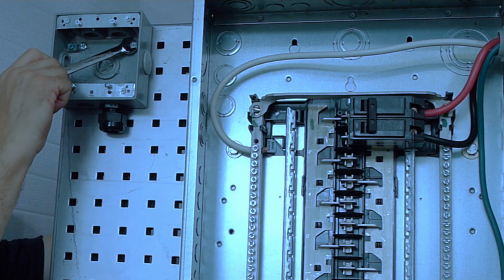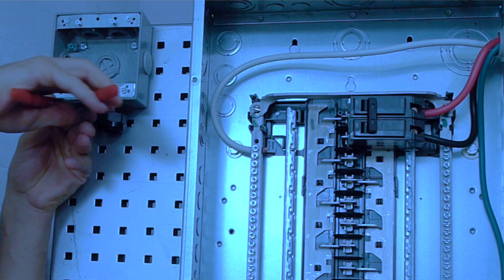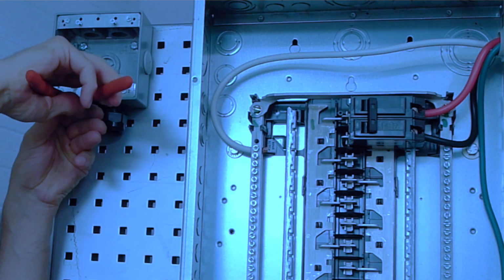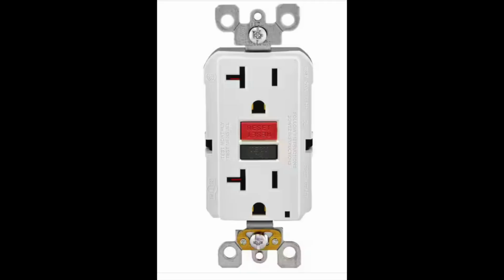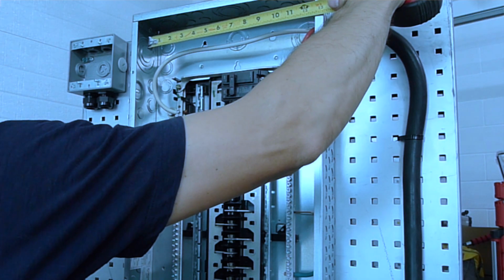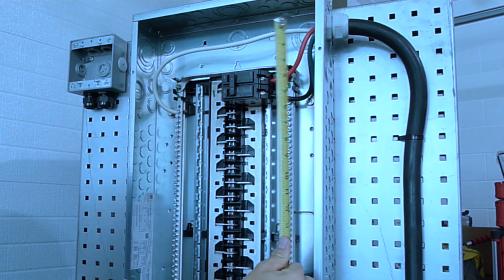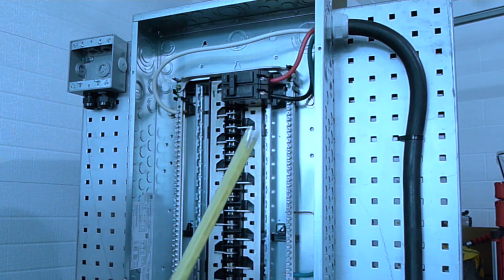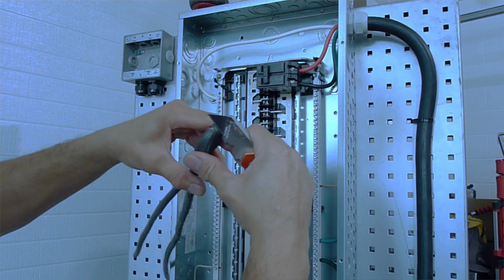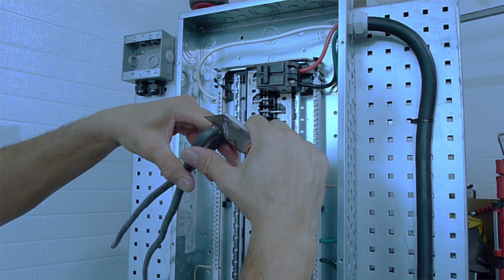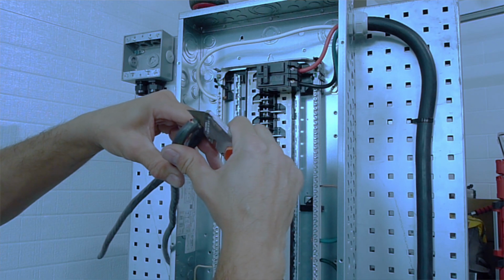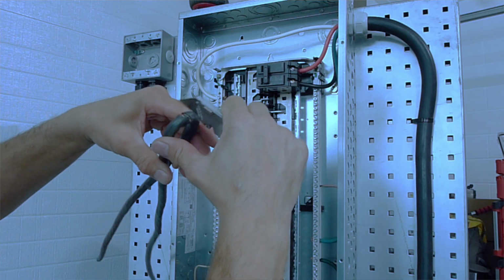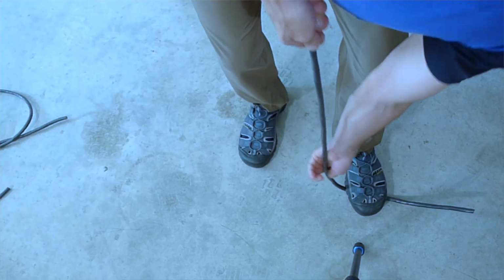At this location, we are securing a 2-gang outdoor box and install 2 GFCI receptacles with 2 designated 20 amp circuit breakers. In this way, we can separately use them and take advantage of the full 20 amp they are rated for. Whenever we are removing insulation on a wire for long distance, I found it easier to step on it and pull it off.